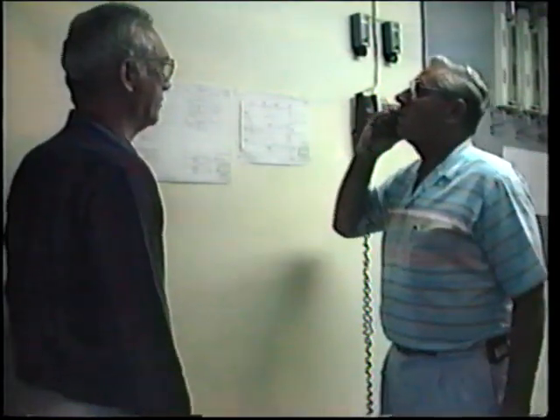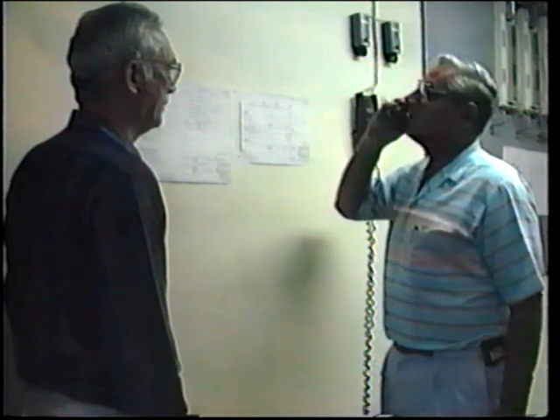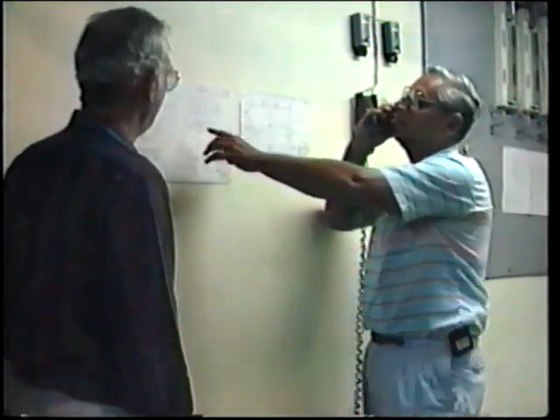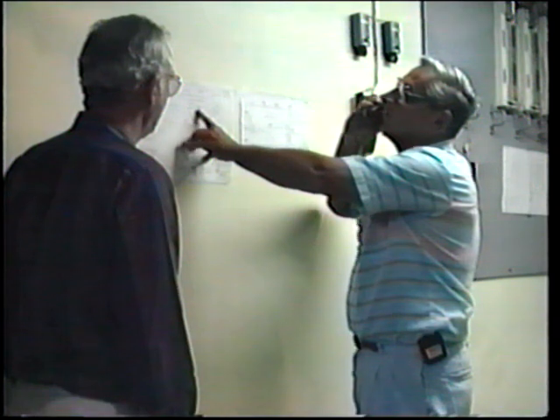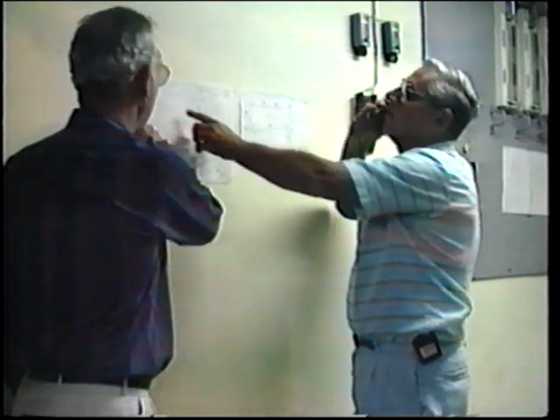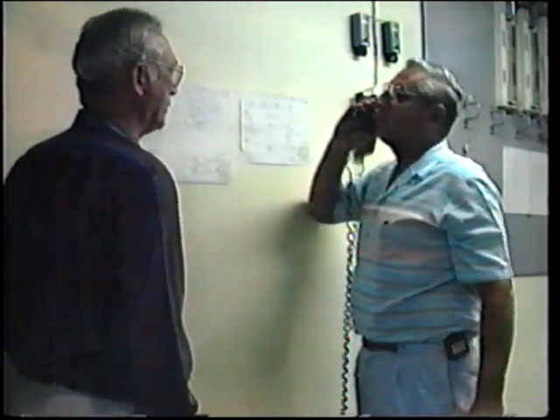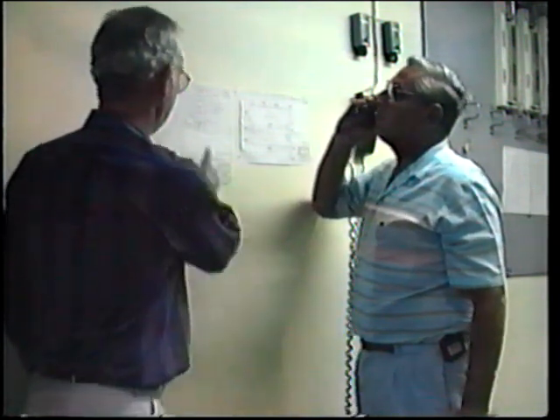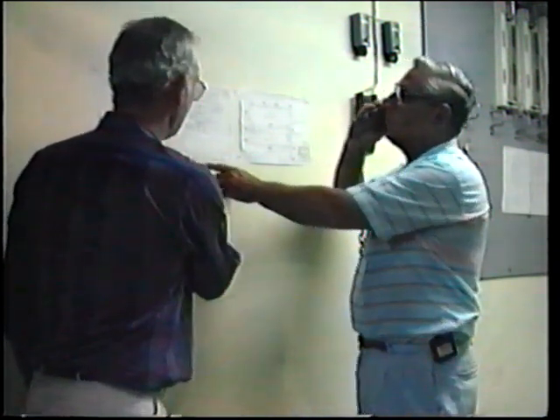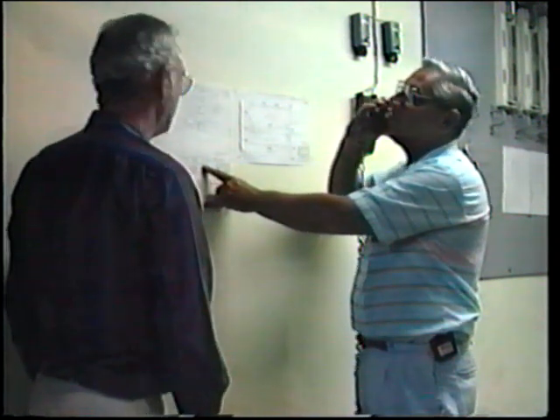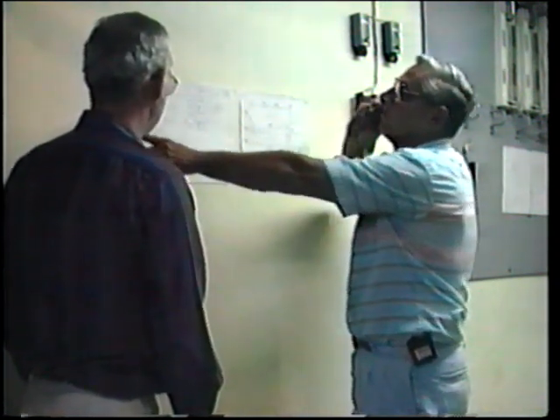Communication is important with operators and also with your own group. This is especially so when performing any critical operation, such as tests of transfer trips or breaker failure schemes. Make sure that messages are clear with no chance for misunderstanding. Try not to use local jargon that may not be understood by other departments, and particularly by other utilities. By far the most important point is for you to be on your toes, follow procedures carefully, know your job thoroughly, and carry it out professionally.